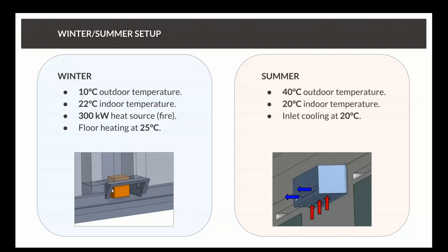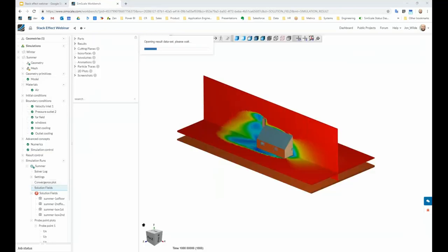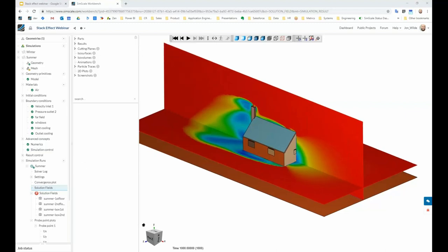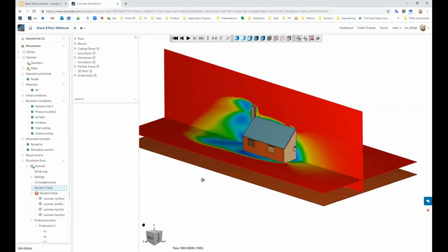Then we have the summer scenario with a much warmer outdoor temperature — like Munich. We want to maintain a nice cool indoor temperature using the cooling units: there's one at the bottom drawing warm air in underneath and kicking cool air back into the room, and we have a couple of those units placed within the building. The main point is that we're trying to force the flow as little as possible and let natural convection work, seeing how natural convection makes the flow enter or exit the room — that's the key idea behind how we set the boundary conditions.